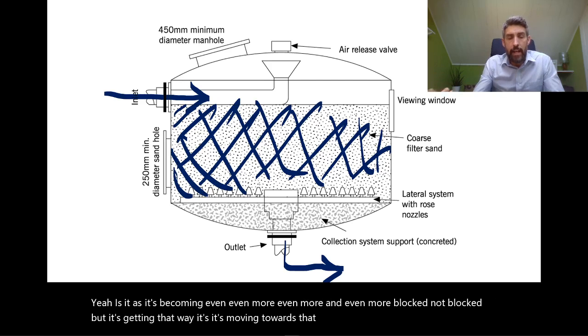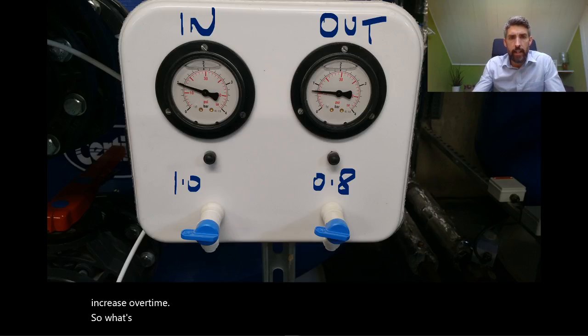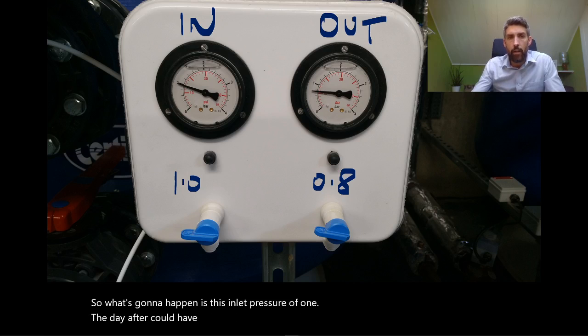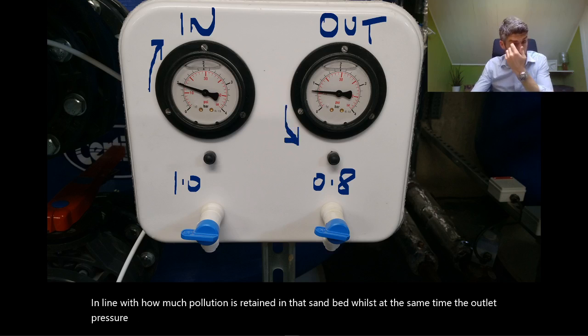The inlet pressure is going to increase over time. What's going to happen is this inlet pressure of one, the day after could have increased to 1.1 because the needle is going to move that way in line with how much pollution is retained in that sand bed. Whilst at the same time, the outlet pressure will move in that direction, so a pressure differential is going to open up.